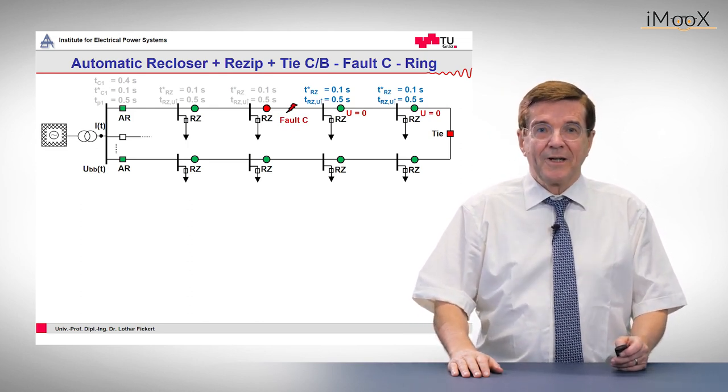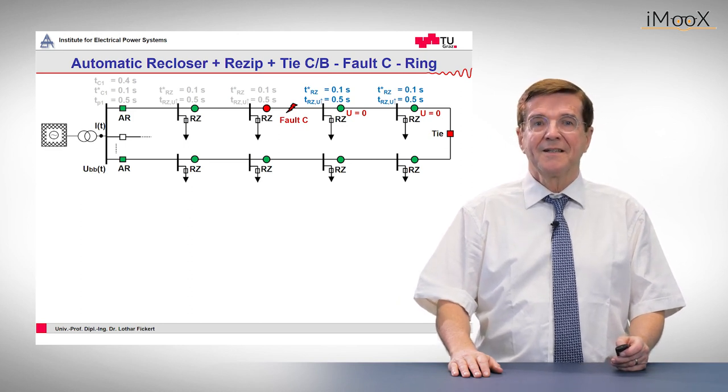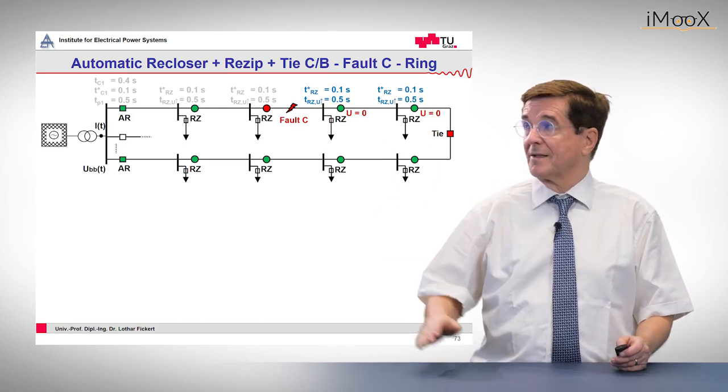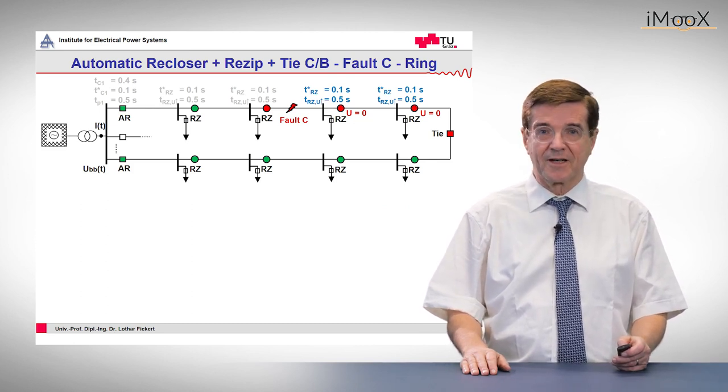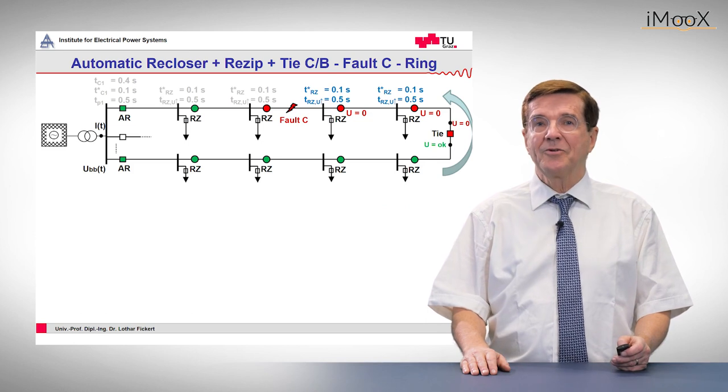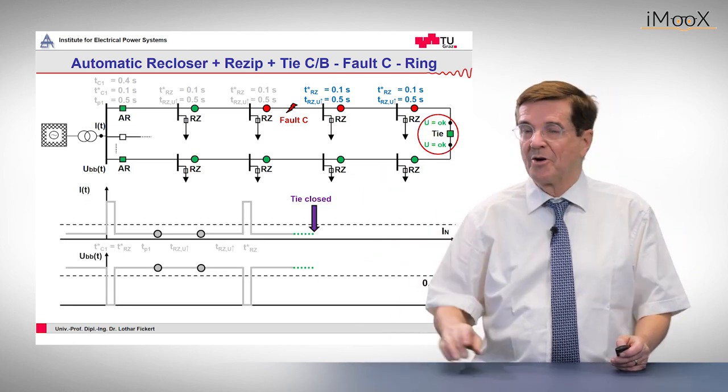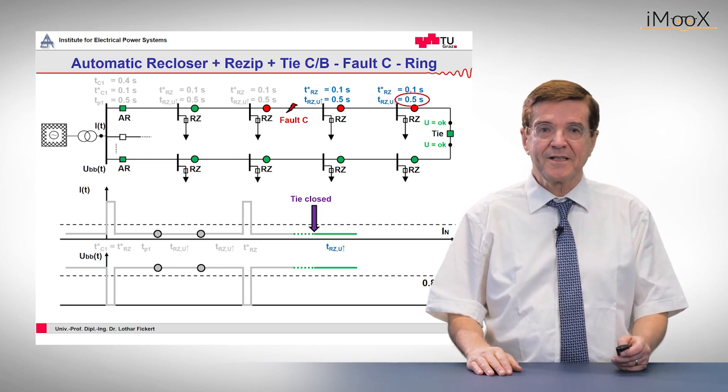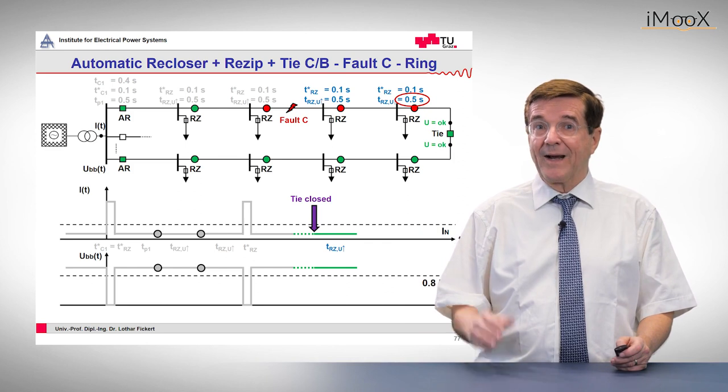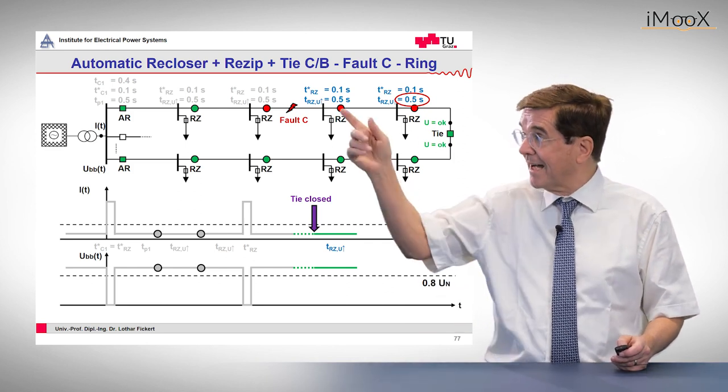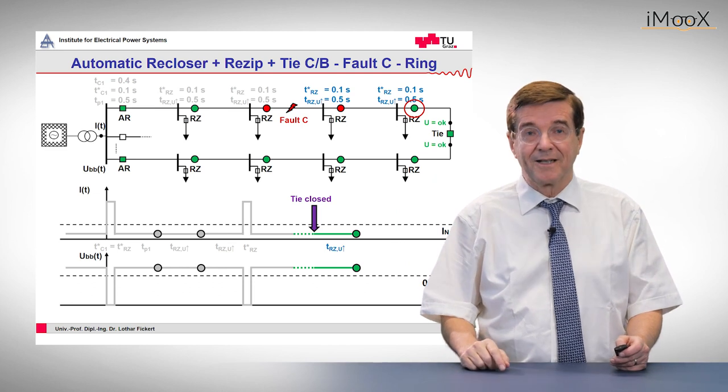So we finish with a fault at position C, as we have seen before. One auto recloser is open, all the others are closed, and now we re-energize the line from the rear side. So this is the moment when the tie breaker closes.